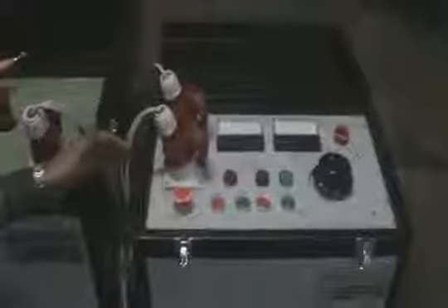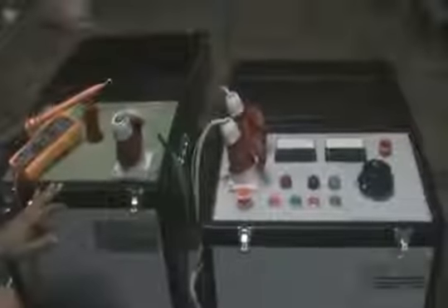Connect both units with the help of the interconnect cable, and make sure that the loading unit is at a far distance from any moving object or not connected with any live parts. Now apply single phase supply 230 VAC to the mains cord. Please make sure that the connections are made with ferruled wires. Earth is compulsory. We have connected the earth terminal of the control unit and the loading unit in the interconnection, so you do not need to give a separate earth to the loading unit.